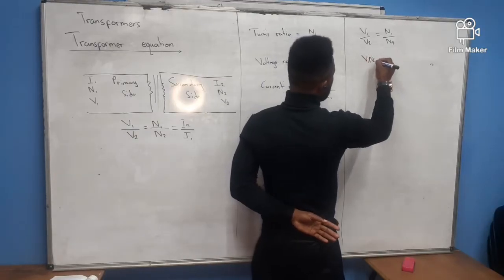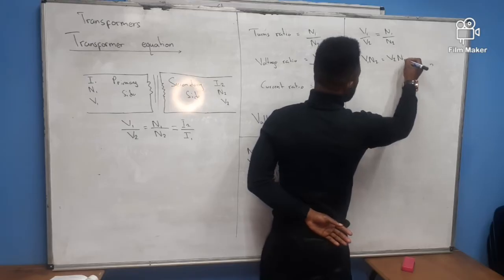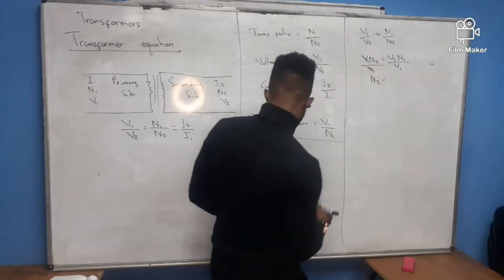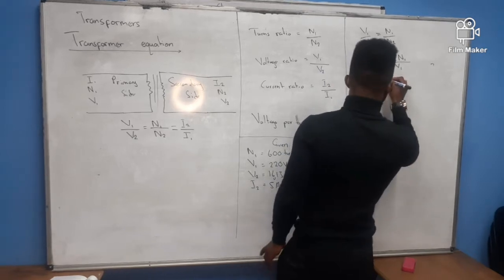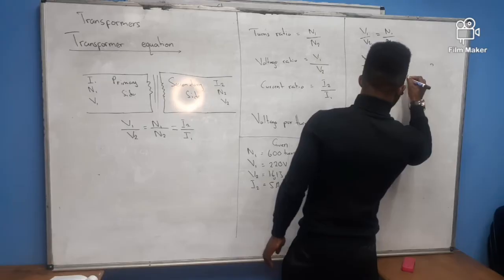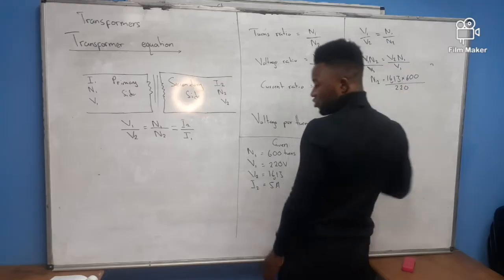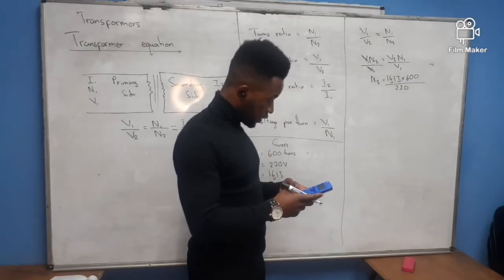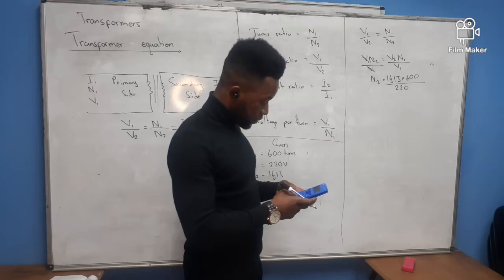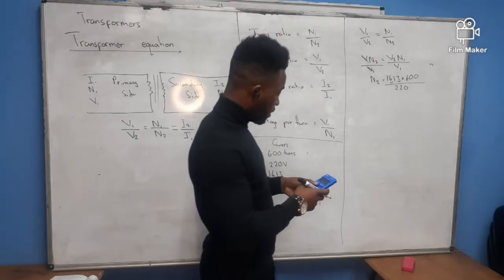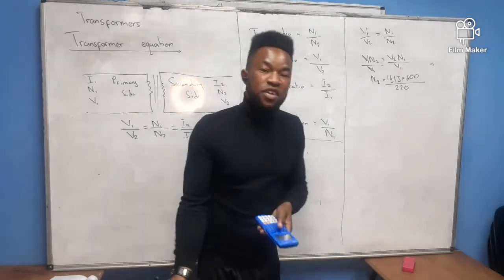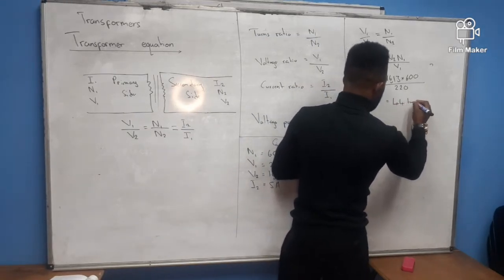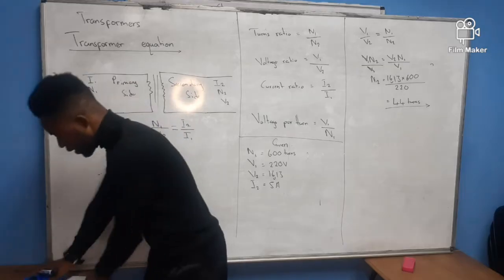Substituting the values: N2 = (16.13 × 600) / 220. Using the calculator, that gives 43.99. Since it's a number of turns, we round off to the nearest whole number, which is 44 turns.